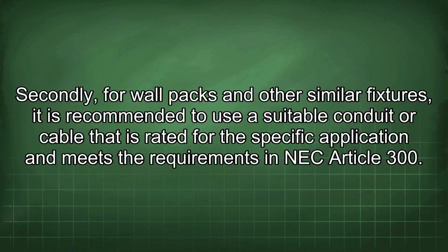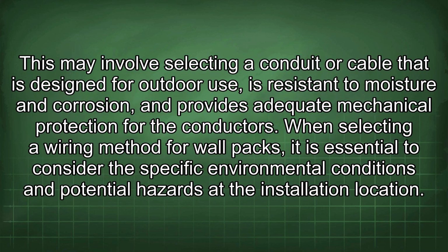Secondly, for wall packs and other similar fixtures, it is recommended to use a suitable conduit or cable that is rated for the specific application and meets the requirements in NEC Article 300. This may involve selecting a conduit or cable that is designed for outdoor use, is resistant to moisture and corrosion, and provides adequate mechanical protection for the conductors.